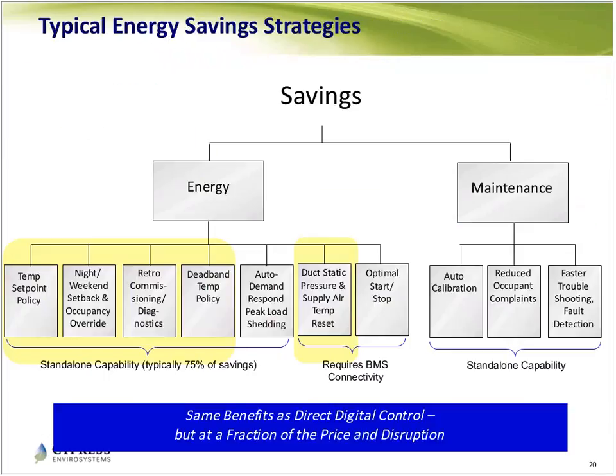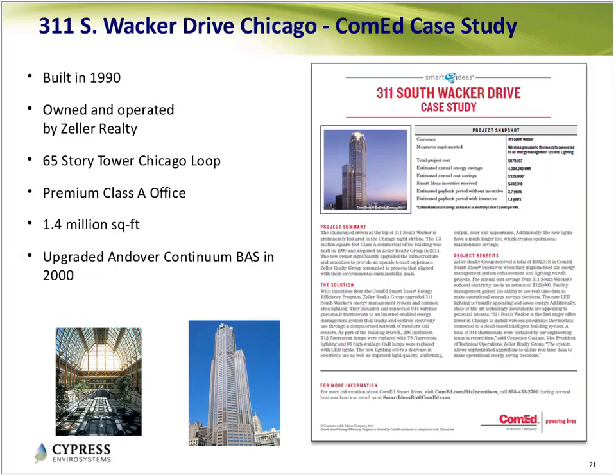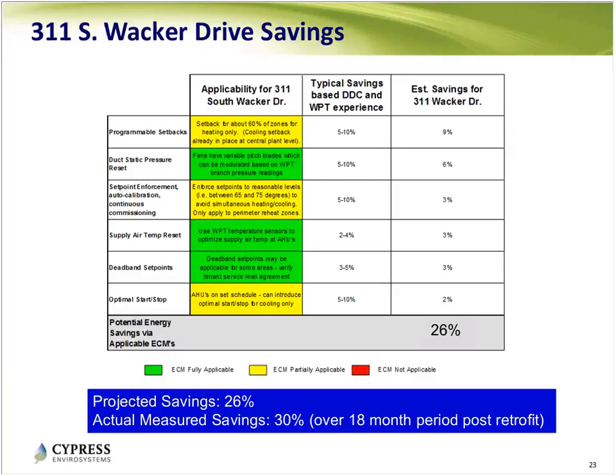I'm going to skip to the savings that you would deploy. As I mentioned, this is all just like digital buildings. You would do these for any digital building, and now you can apply these savings to pneumatic buildings at a much lower cost. You wouldn't have to spend as much money to enable your building to do these strategies. So once you put in the strategies, typically we would save about 20 to 30%, with a minimum of 15% typical.